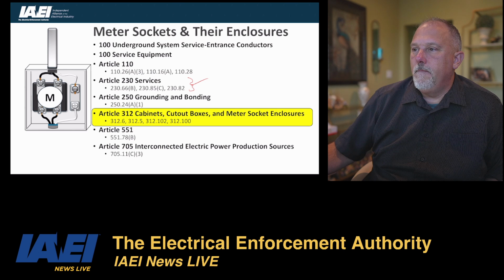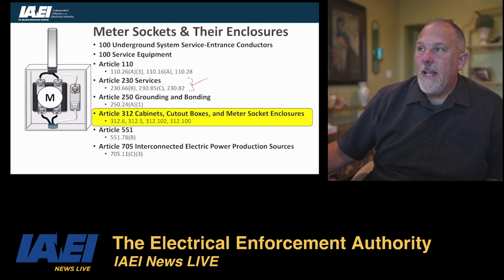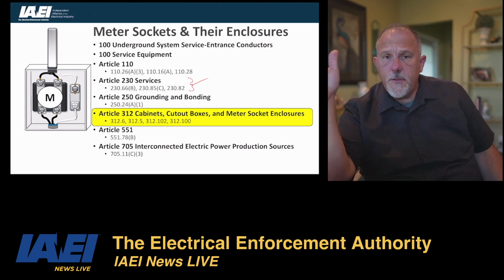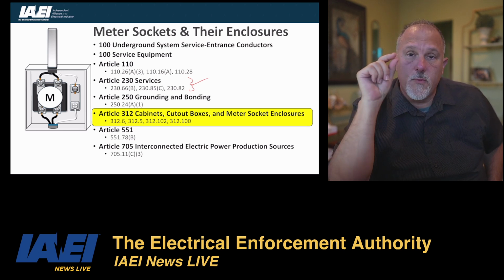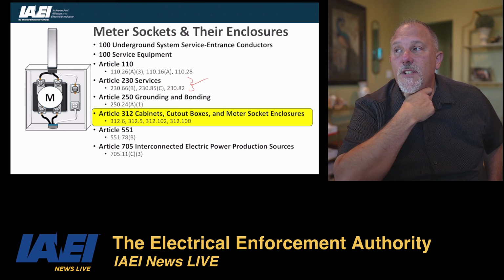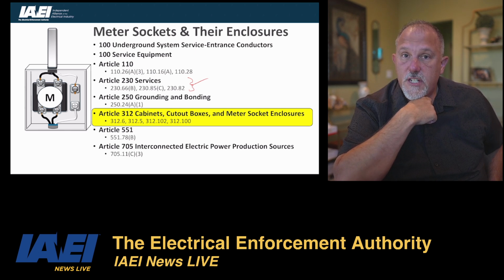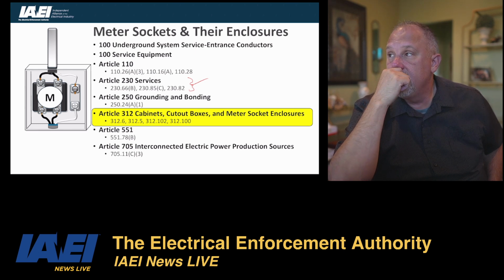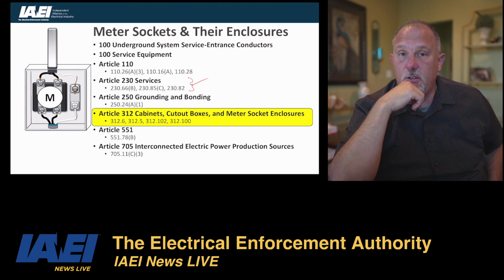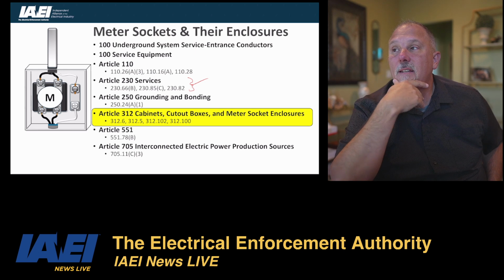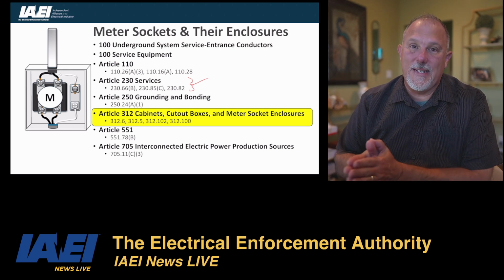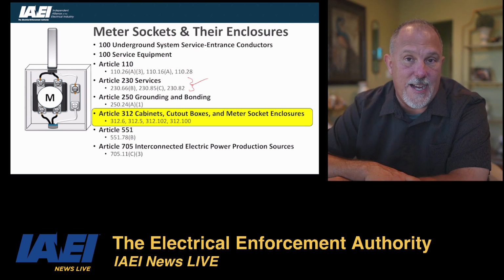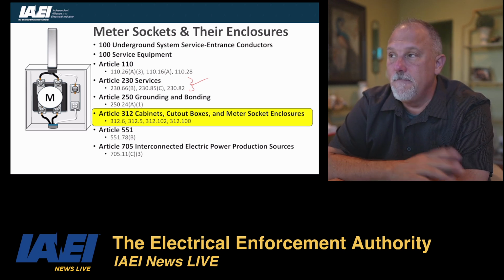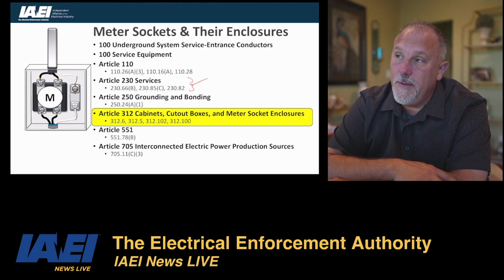In 230.85(C), emergency disconnect, this is in the 2023 code, it's titled replacement. What it says is, where service equipment is replaced, all of the requirements of this section shall apply. Where service equipment is replaced. Now, if you're adding on to an existing installation and you put a transfer switch outside and it now becomes your service equipment, I would say you're probably meeting that requirement.